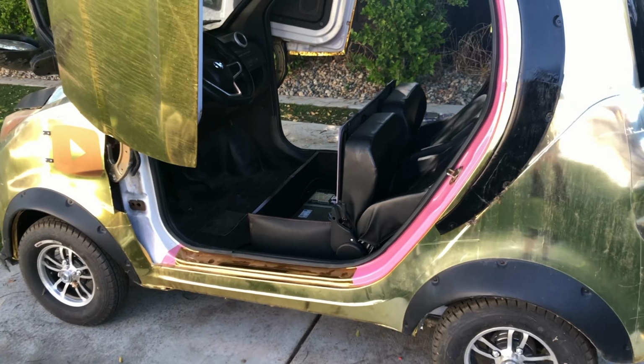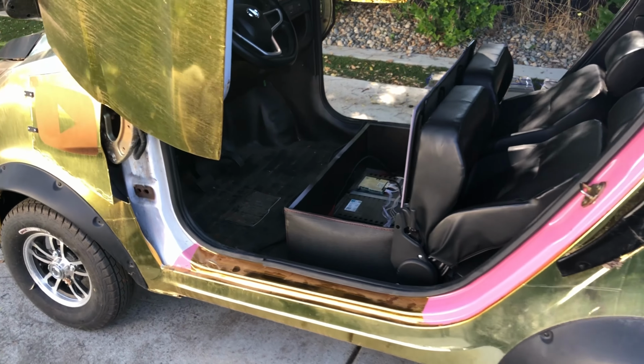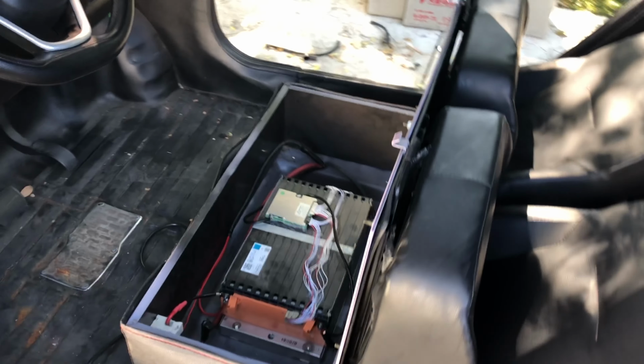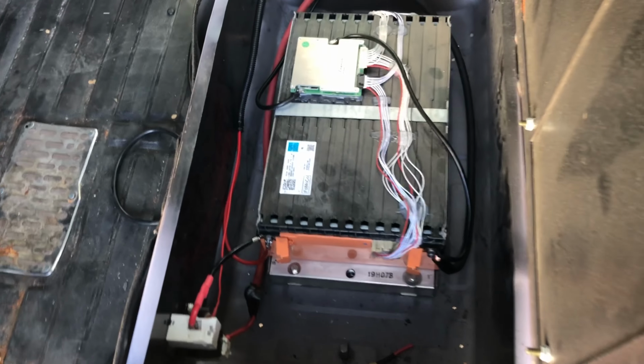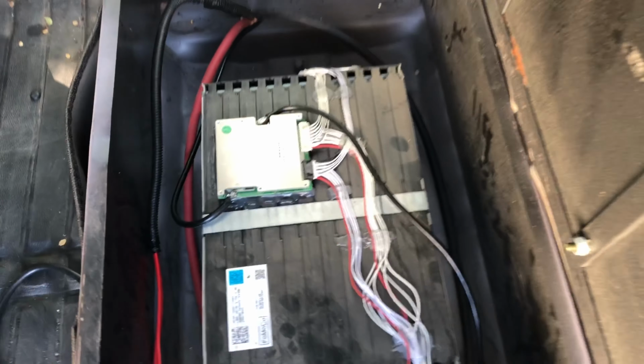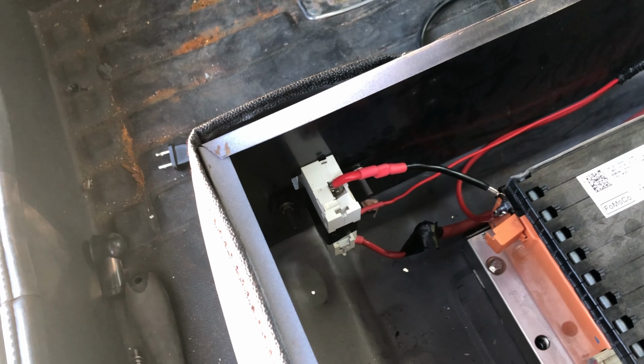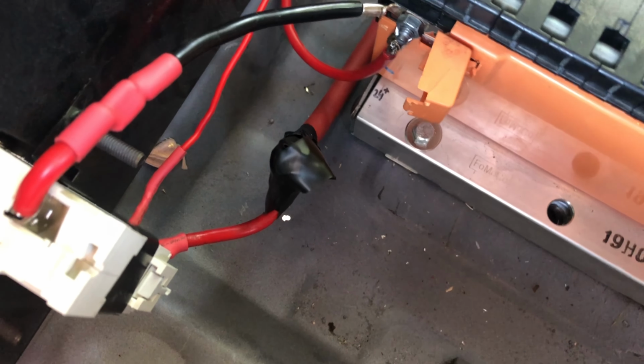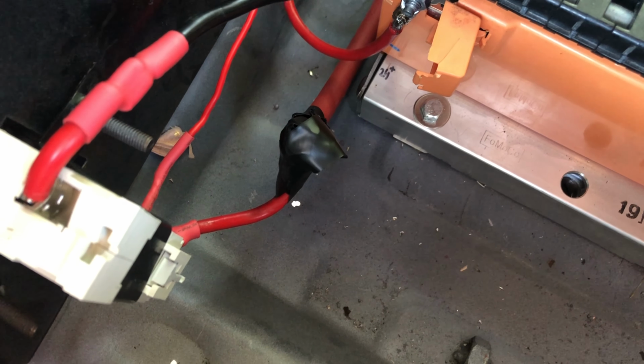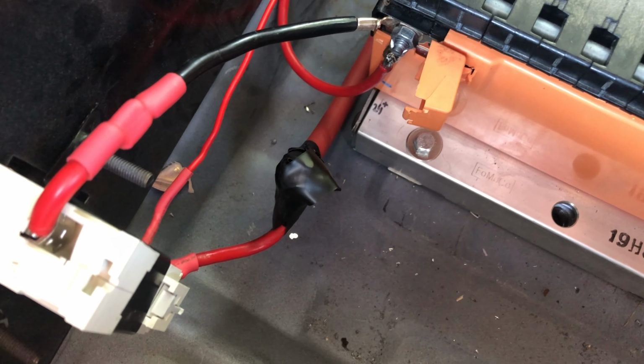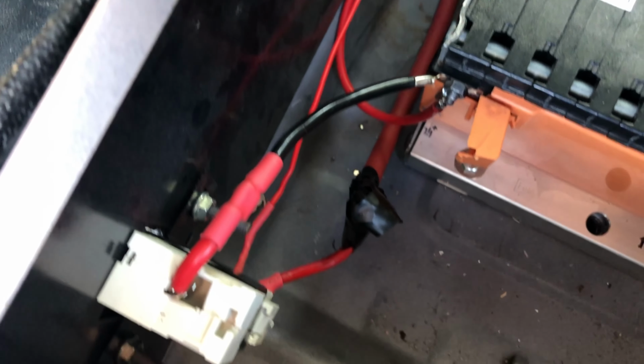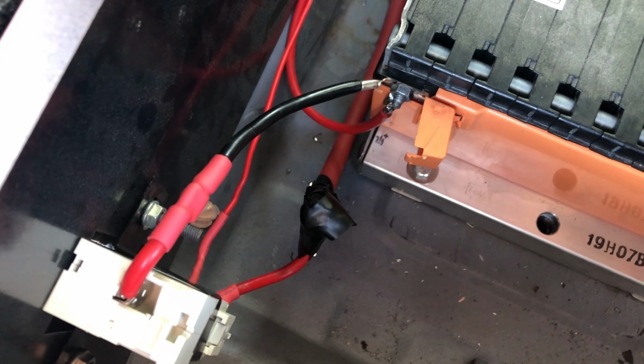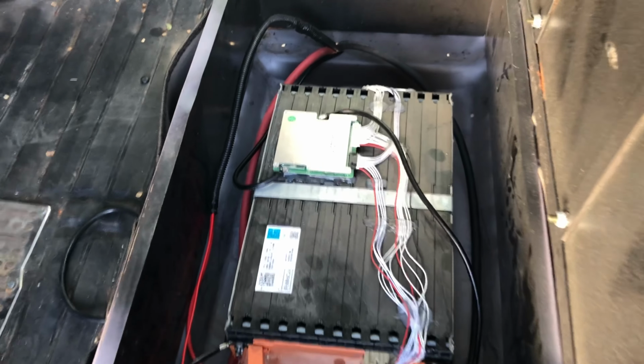All right guys, I got this thing all fixed up as far as my expertise is concerned. Obviously it's going to get a beautification still and all that, but got the battery installed and BMS hooked up, discharge cables running through the original circuit breaker. But I did just connect the positive discharge to the ring terminal coming off of the circuit breaker, because if we end up frying that or blowing out these wires like a fuse — since there's like 8-gauge wire — I can just untape that and bolt it straight on. So we do have the ability to bypass it if it becomes a problem, but for now we're going to have it running through there.